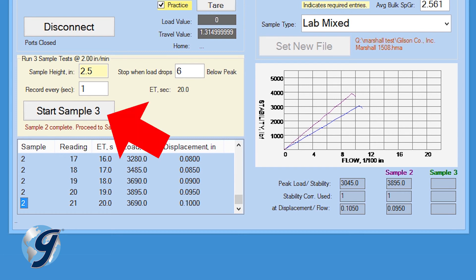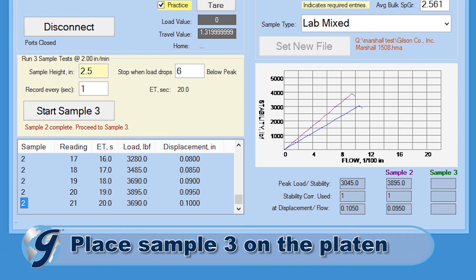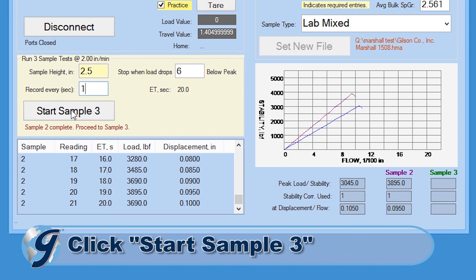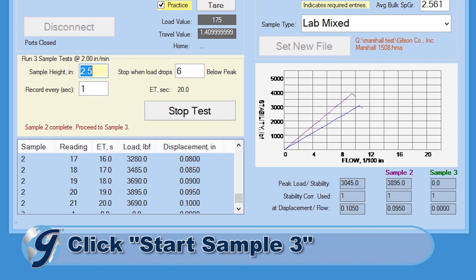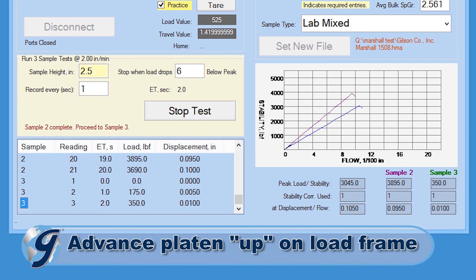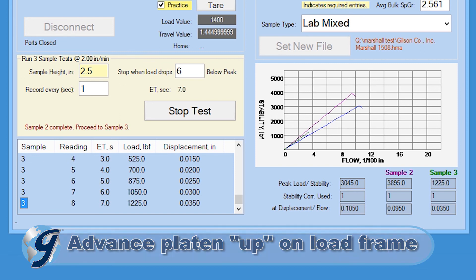A start sample 3 button will appear. Seat sample 3 on the platen. Change the sample height value in the sample test tile for the third sample. Click start sample 3. On the load frame, switch the platen advance up and the program will again begin recording data.